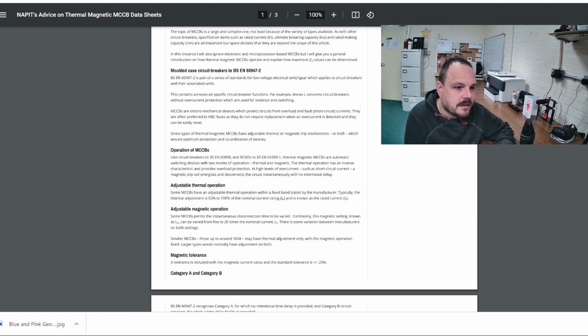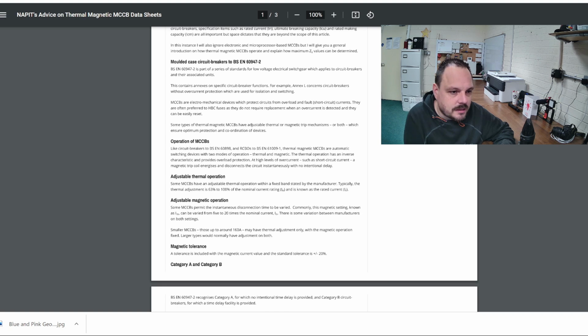So it says here the operation of MCCBs, like circuit breakers, so your 60898s and your RCBOs 61009, thermal magnetic MCBs are automatic switching devices with two modes of operation, thermal and magnetic. The thermal operation has an inverse characteristic and provides overload protection, which we spoke about earlier on in the video, and high levels of overcurrent such as short circuit current. A magnetic trip coil energizes and disconnects the circuit instantaneously with no intentional delay.